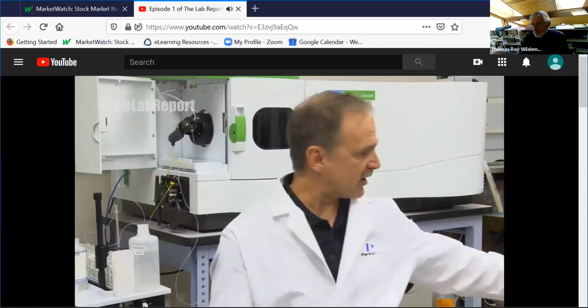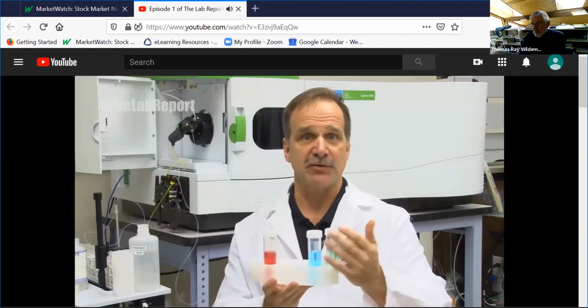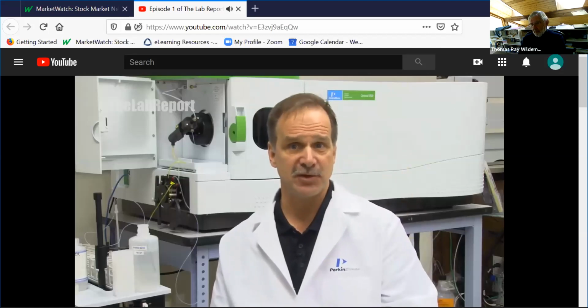The next thing that you have to worry about, when we were talking about all these different elements that we're having in the solution, whether it's copper, nickel, iron, cobalt, chrome, is that you have a very complex spectrum. For example, just iron has thousands of emission lines itself. Add in chrome and nickel and others that have a lot of emission lines, and very soon you have an incredibly complex spectrum. There's a pretty good chance that those lines are going to overlap or interfere with the elements or the analytes of interest that you're trying to measure.